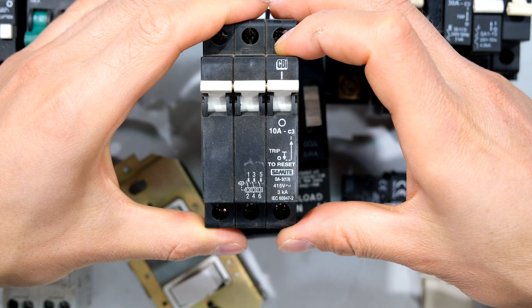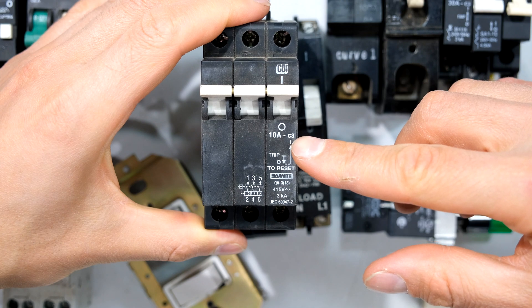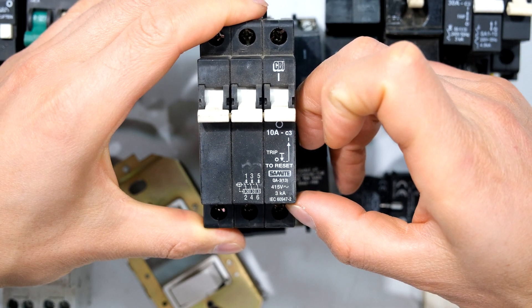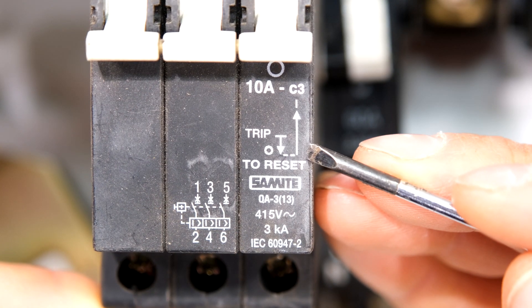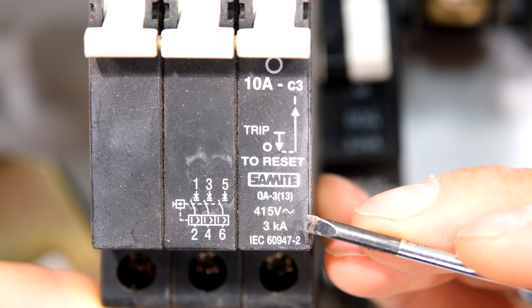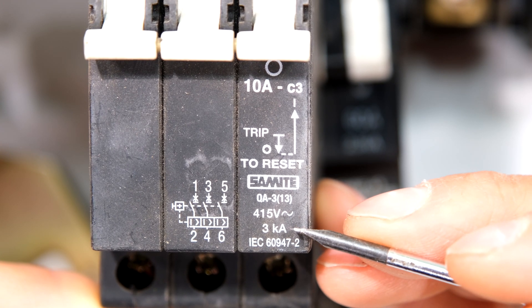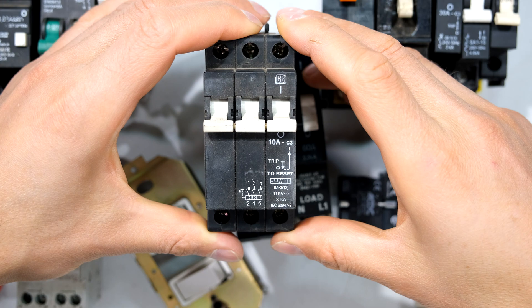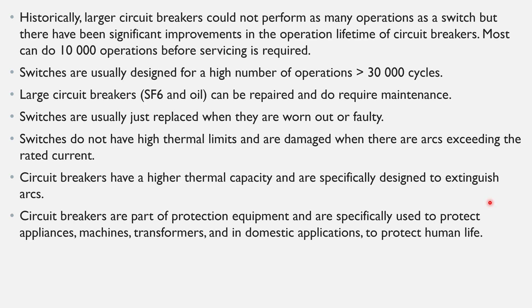A circuit breaker is different. It says 10 amps on this one, meaning at 10 amps it will automatically trip and open the circuit. But on the front or side of the circuit breaker we see additional values — it says 3 kilo-amps, meaning this circuit breaker is able to deal with a fault current up to 3,000 amps.